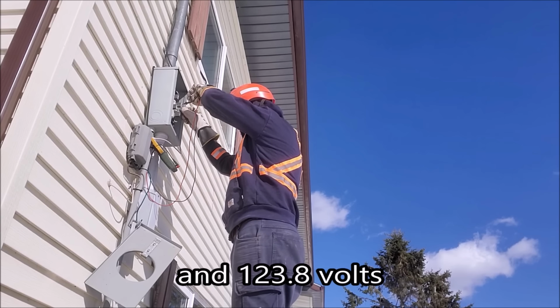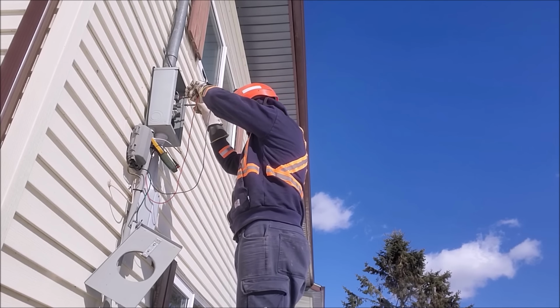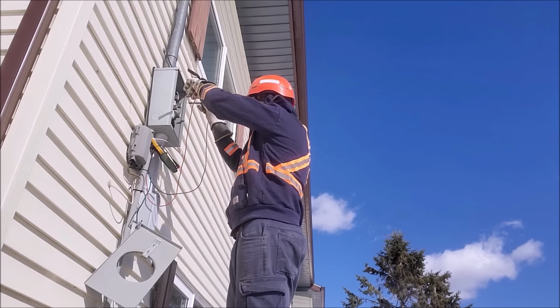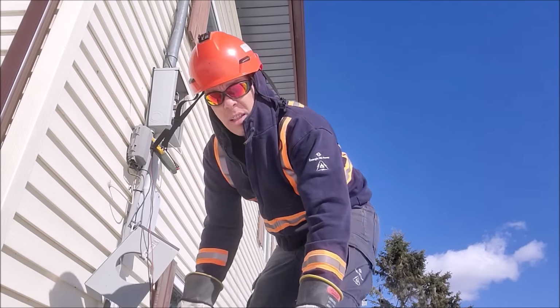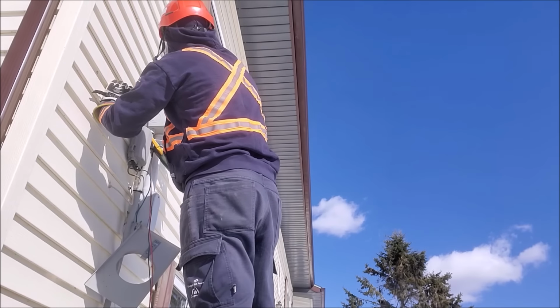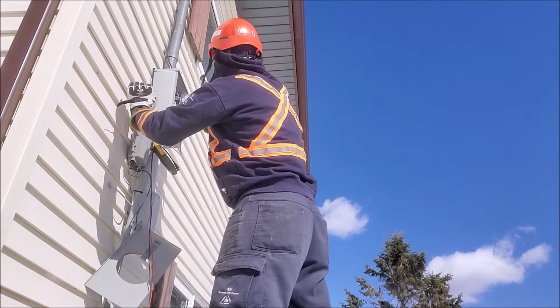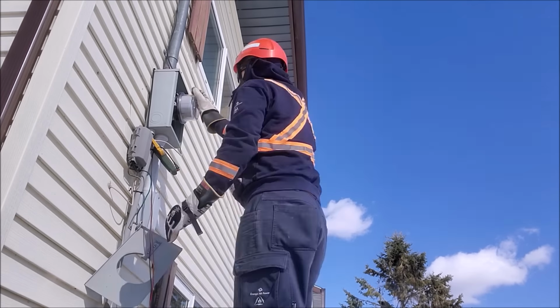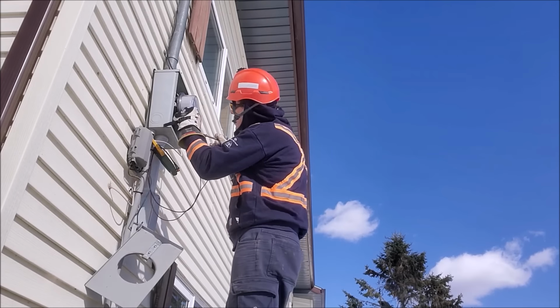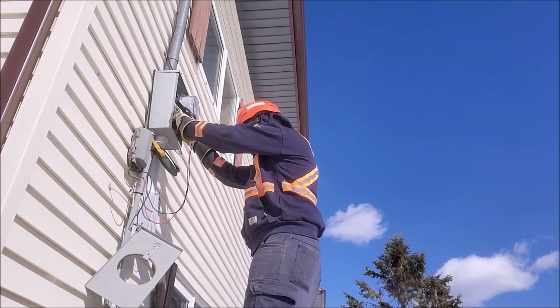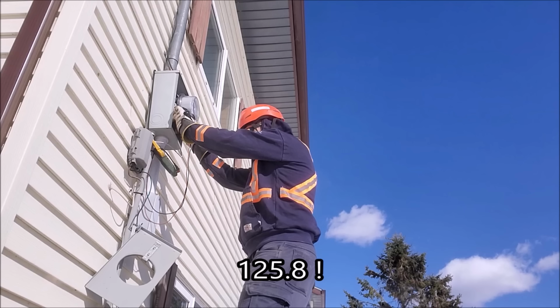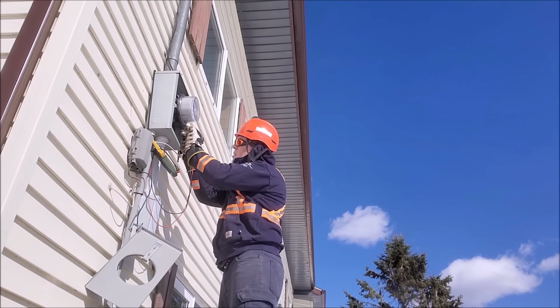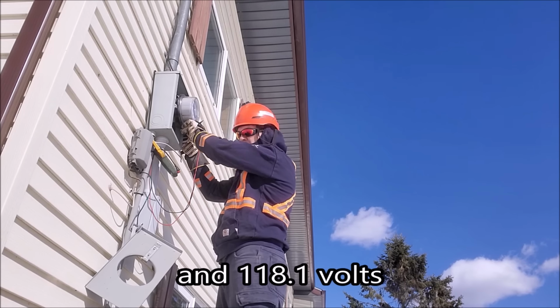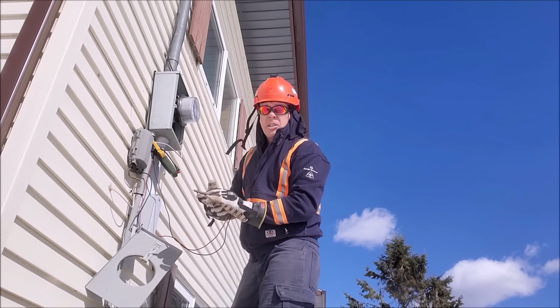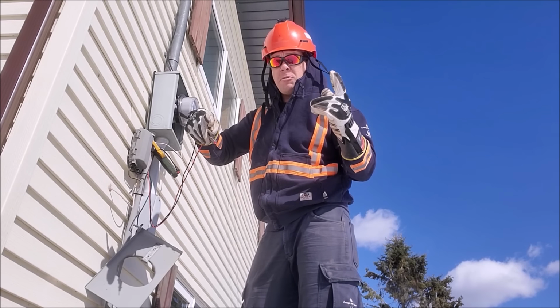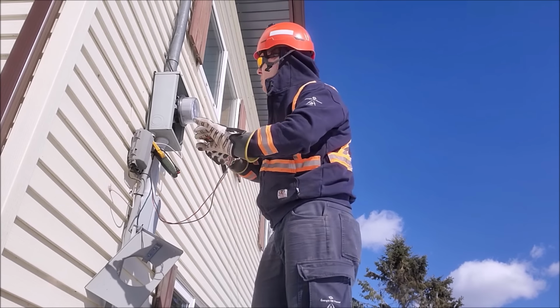123.8 and 123.8, that's easy enough. 247.7. Let's get that meter on there. 123.8 and 118.1 — so it went up 2 or 3 volts on one phase and down 2 or 3 on the other. That's definitely a bad neutral.